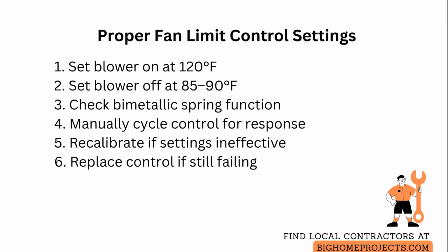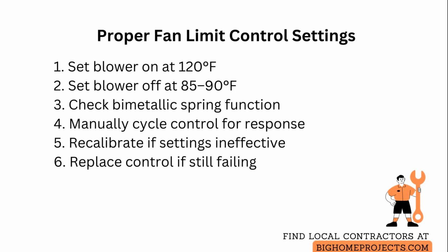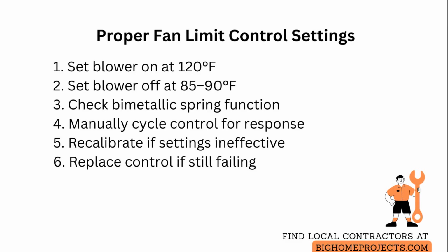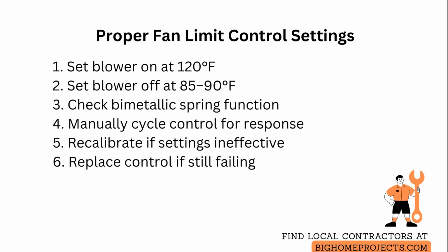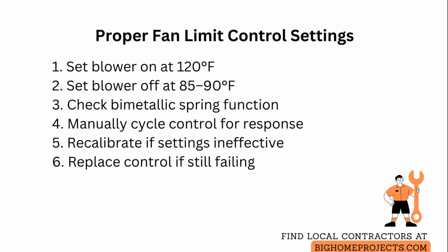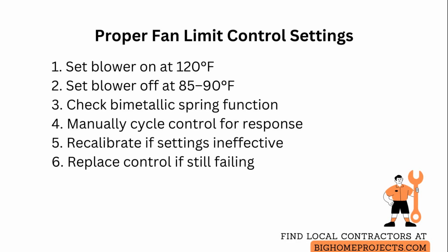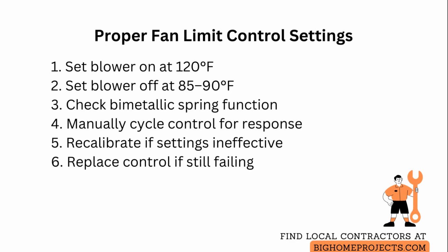Verify the bimetallic spring inside the control is functioning by manually cycling the control and watching for a crisp response. A sluggish or no response indicates the spring has weakened or is stuck. If the set points change the blower behavior only slightly or not at all, recalibrate the limit control using the manufacturer's adjustment procedure or replace the control with a new unit matched to the furnace model and heat rise requirements.